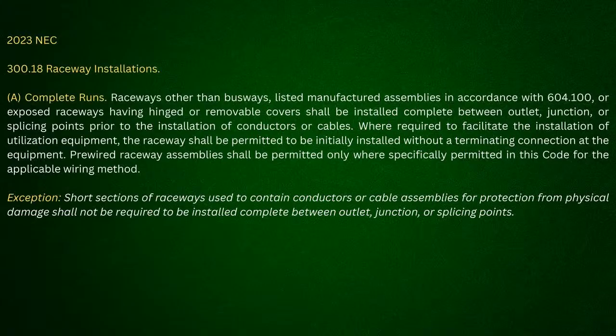It says it's a complete run in 300.18a. And it says raceways other than busways, listed manufacturer assemblies in accordance with 604.100, or exposed raceways having hinged or removable covers shall be installed complete between outlet, junction, or splicing points prior to the installation of conductors or cables. Okay? Yeah. I didn't make anything up.